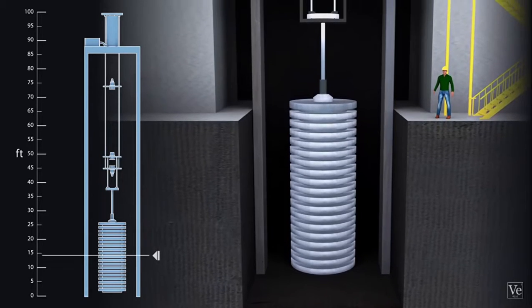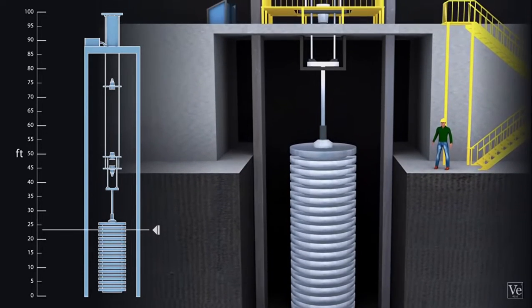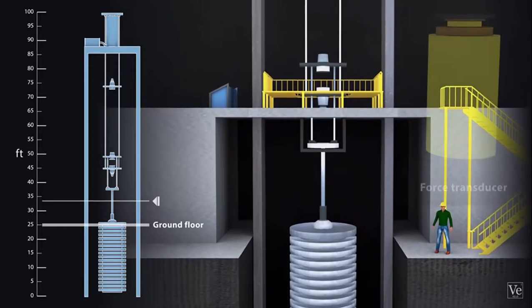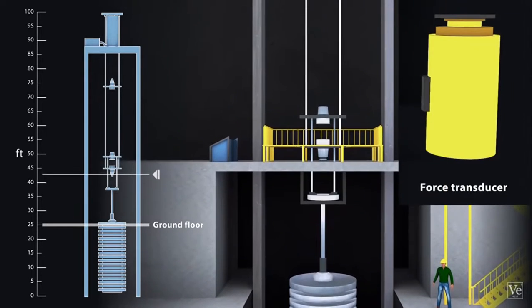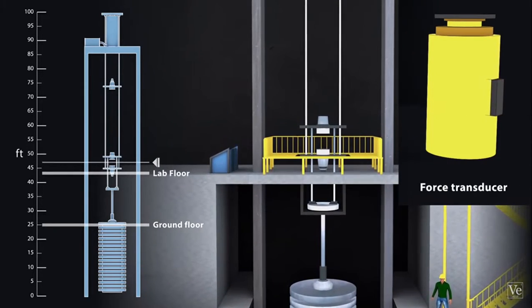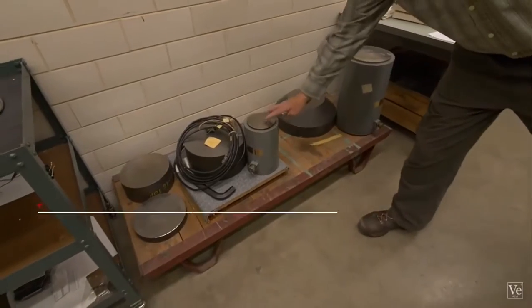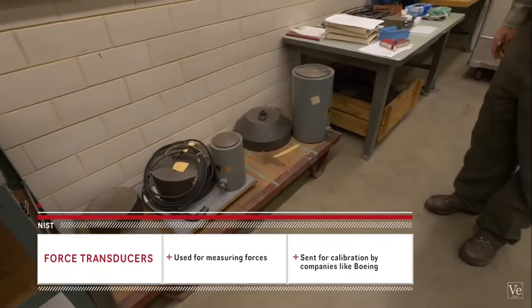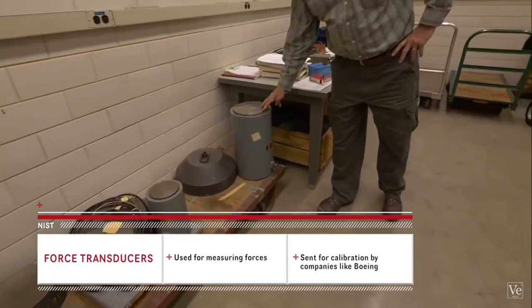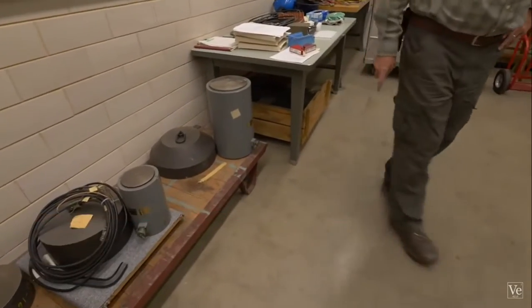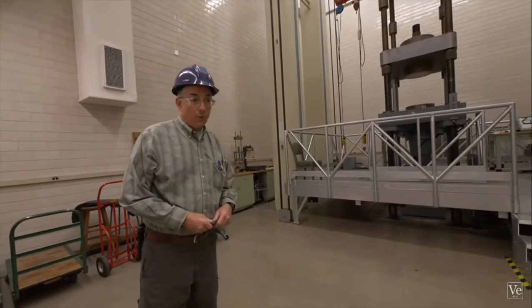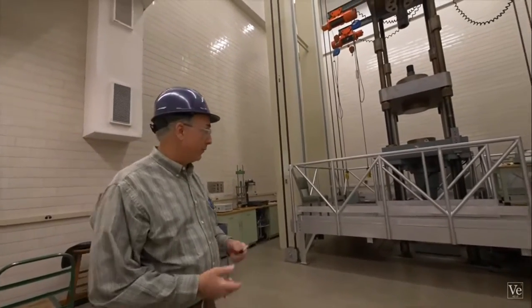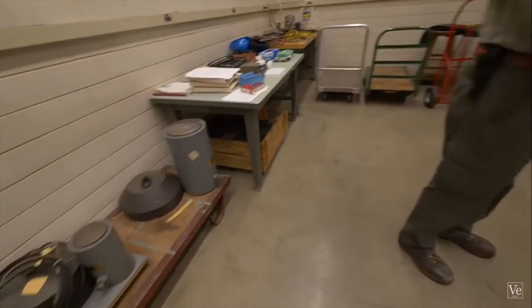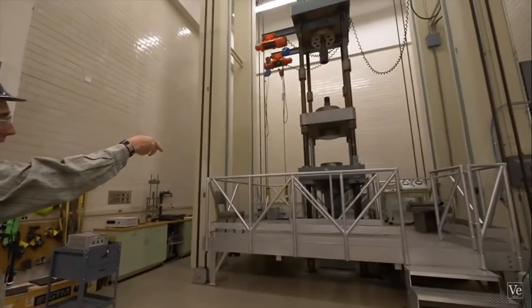The machine works like this. Below ground are the 20 carefully calibrated masses. Their weight is used to calibrate force sensors, also called force transducers, in the lab upstairs. This is a 1 million pound capacity, 4.45 meganewton, and this is 13.3 meganewtons, 3 million pounds force. This is the biggest machine of its type in the world, and obviously one of a kind.